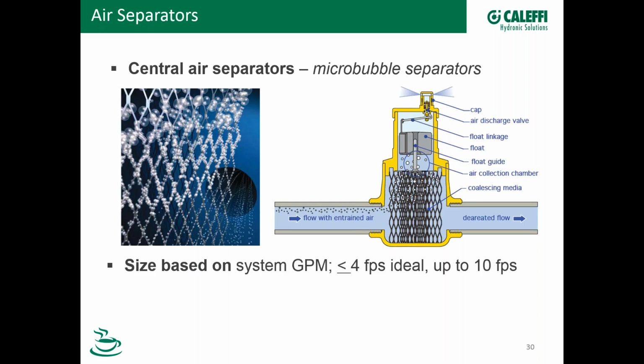We get the question on what size of an air separator to pick. I think this is one of the pre-submitted questions actually. What we suggest is that 4 feet per second or less is ideal. And you can go up to 10 feet per second in velocity, especially in your larger flanged units, because those are big pipes, and even in chilled water systems, for example, we tend to have higher velocities. So up to 10 feet per second is still okay. You'll still get air removal, and the coalescing elements will still scrub out that air at that velocity, at least in our products. That's what we say.